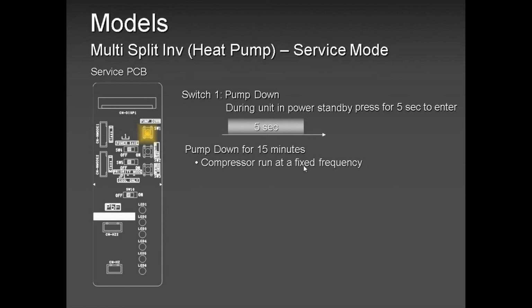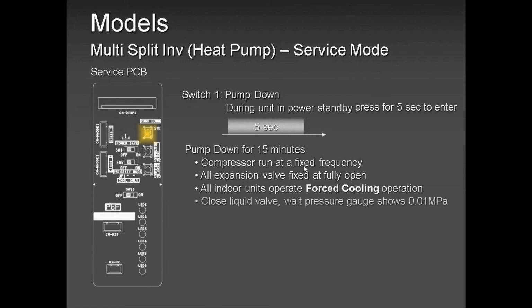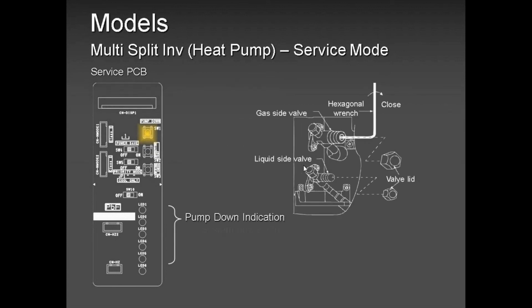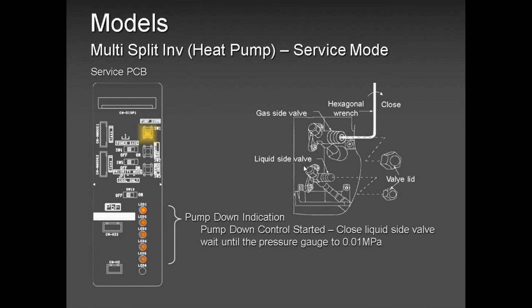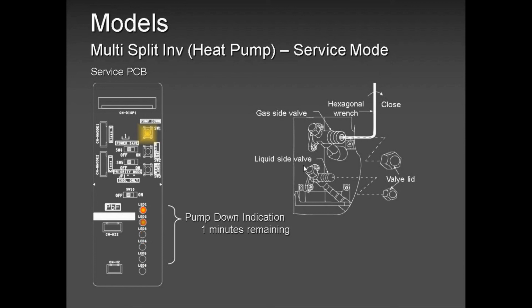So when you look at the service PCB, you have many features that it takes care of. It can pump down. So let's say the homeowner is not at home and you need to do some work that involves pumping down. You can do a pump down even if the homeowner is not at home. If you call the homeowner and the homeowner says, I'm on my way, I'll take about an hour, you can do at least your pump down, you can start your work, no problem. Open up the outdoor unit, press that button for 5 seconds, pump down begins.